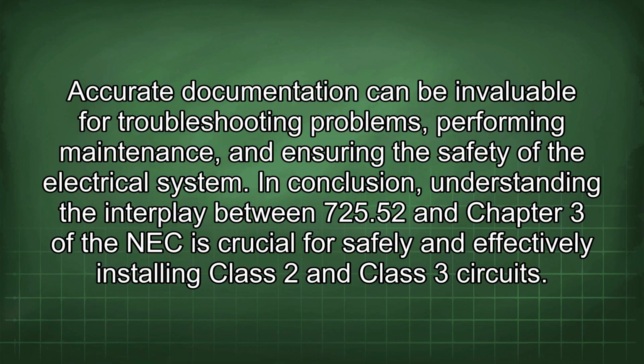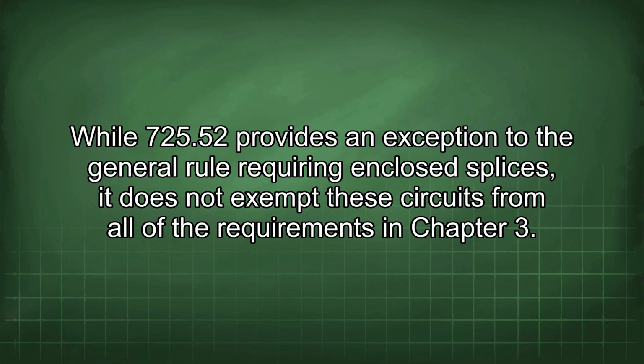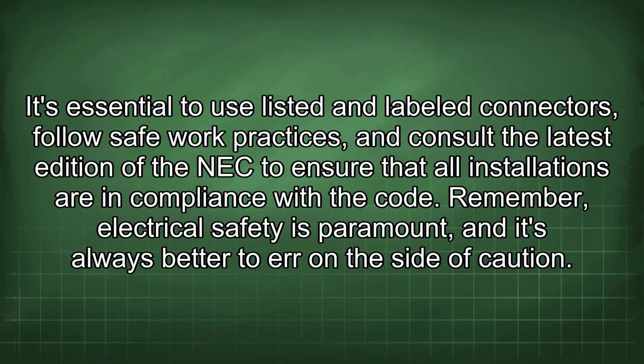In conclusion, understanding the interplay between 725.52 and Chapter 3 of the NEC is crucial for safely and effectively installing Class 2 and Class 3 circuits. While 725.52 provides an exception to the general rule requiring enclosed splices, it does not exempt these circuits from all of the requirements in Chapter 3. It's essential to use listed and labeled connectors, follow safe work practices, and consult the latest edition of the NEC to ensure that all installations are in compliance with the code.